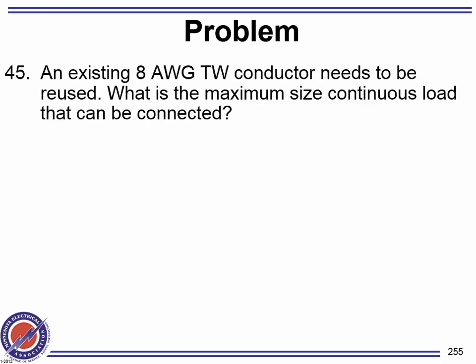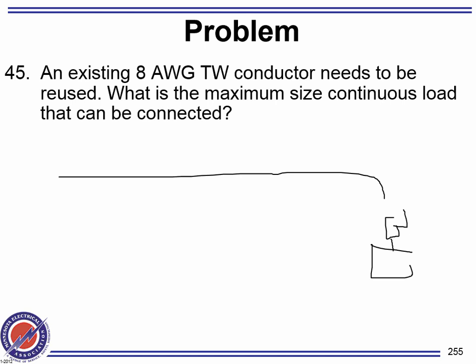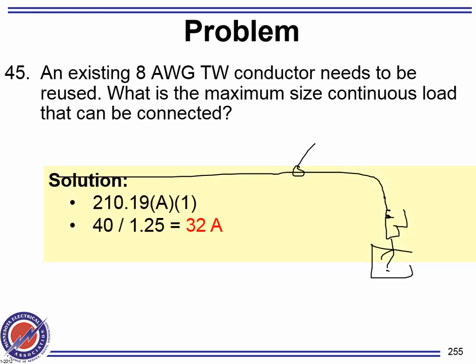Okay. Existing number 8 conductor needs to be reused. What is the maximum? I have a cable right here, it's already existing, and I need to tie a machine to it, through a fused disconnect, and land it on a machine. What size machine can I put on it? It's a continuous load, so what do you do? You find the amps, and you rate it by 80%. Or here's what you do. TW can get you 40 amps, and it can get you 32.